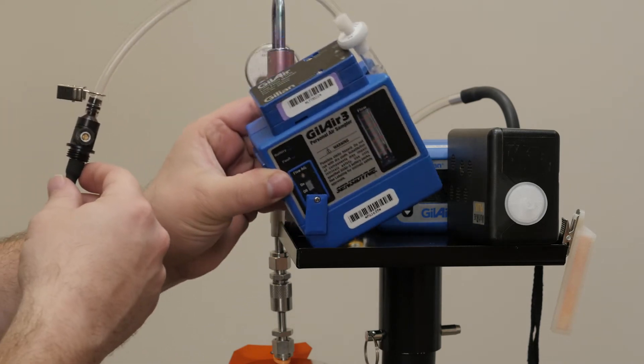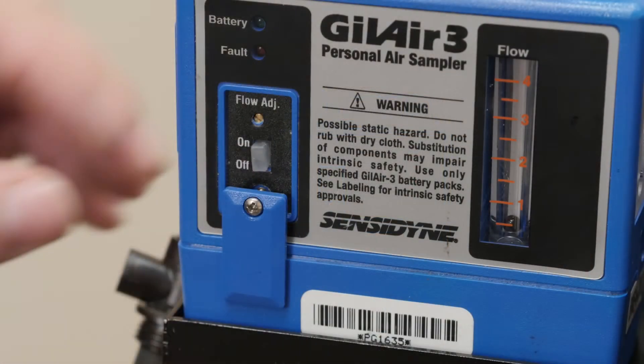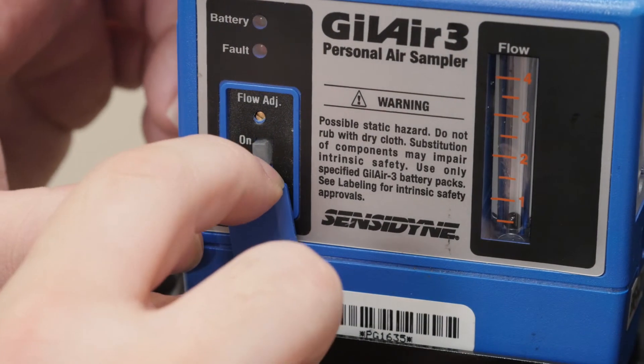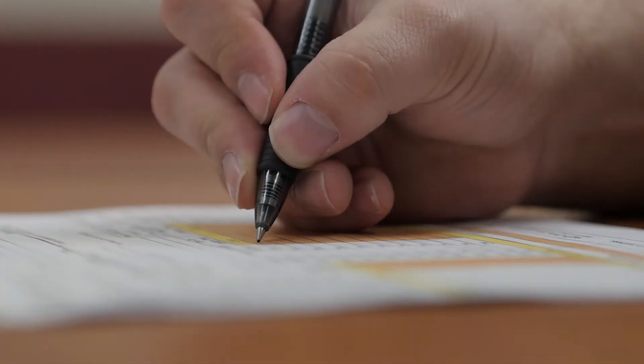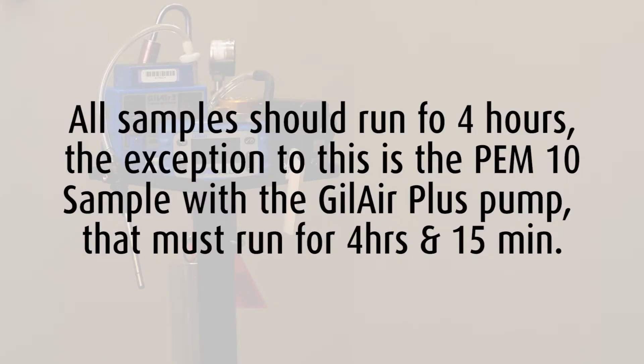Place the pump on the sampling tray. Turn on your pump and indicate the start time on your chain of custody. All samples should run for four hours. The exception to this is the PEM-10 sample with the GilAir Plus pump, which must run for approximately 4 hours and 15 minutes.